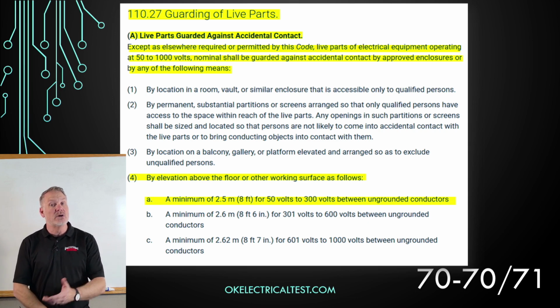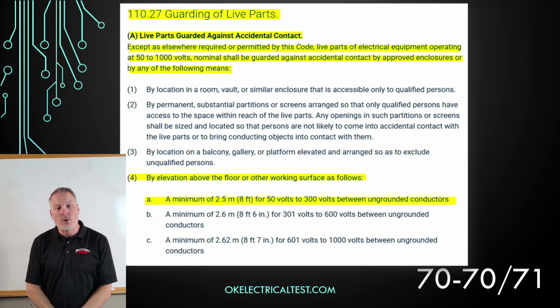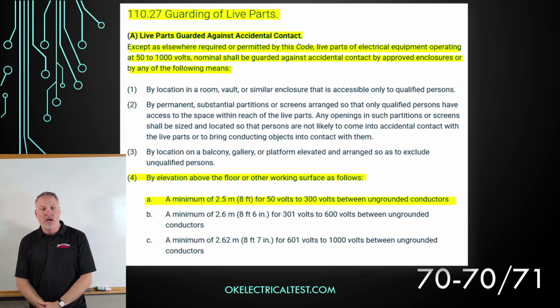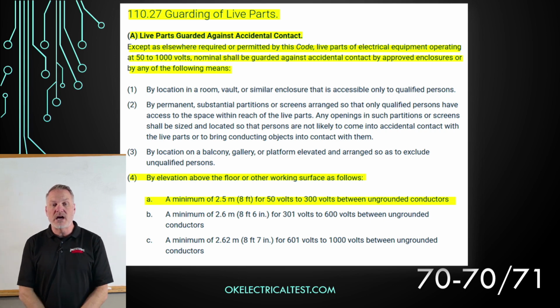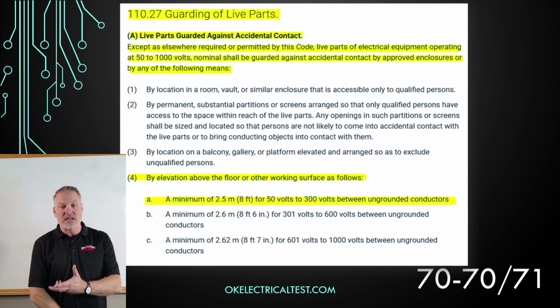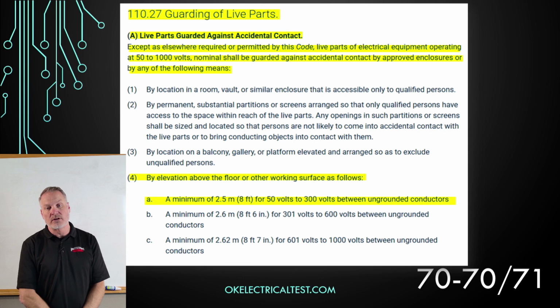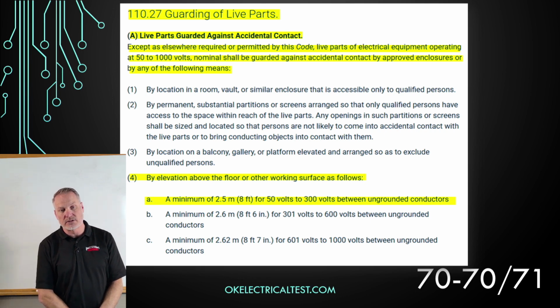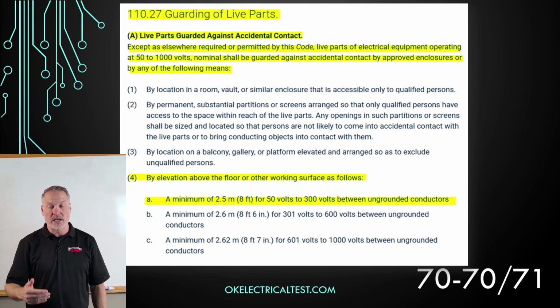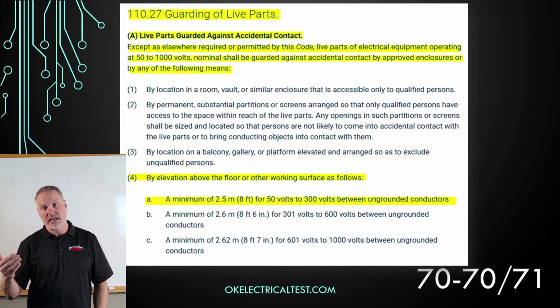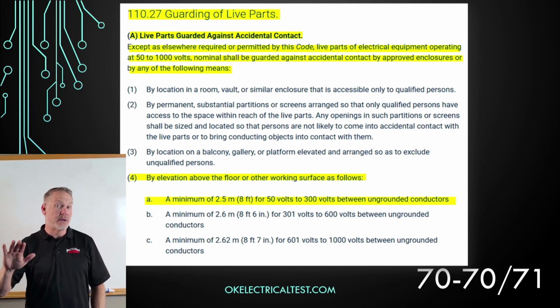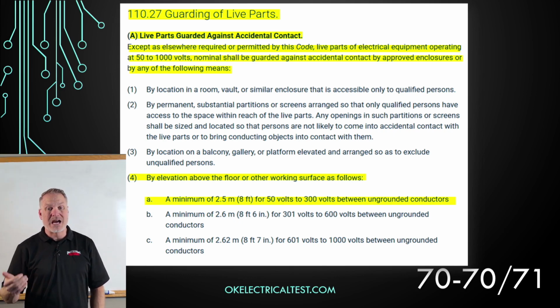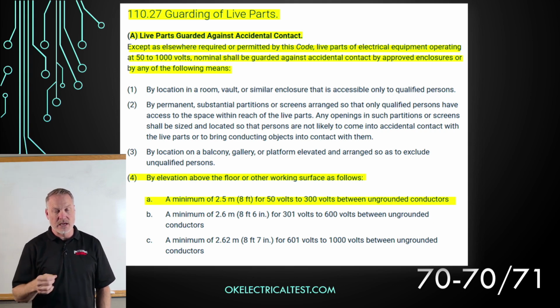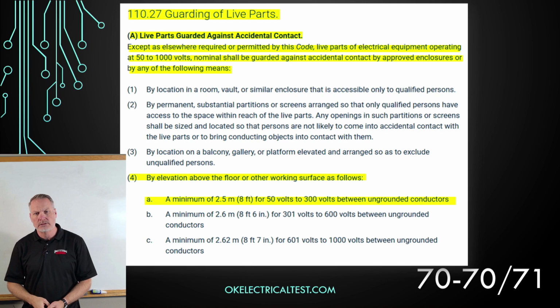Now it says also it can be guarded by any of the following means. We're going to jump down to number 4. It says by an elevation above the floor or working surface as follows: a minimum of 8 feet for 50 volts to 300 volts between ungrounded conductors. And so one of the ways we can guard against that is by elevating it. How high do we need to elevate it? Depends on the voltage, right? If I'm not exceeding 300 volts, we can elevate that 8 feet, and that would be considered adequate guarding.